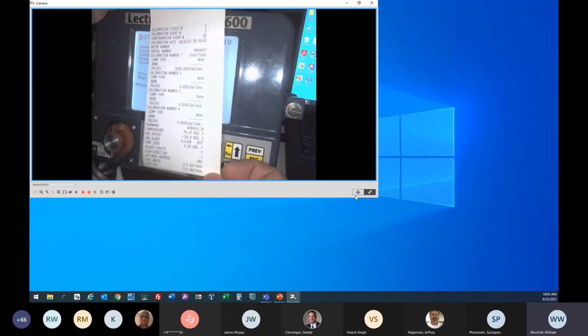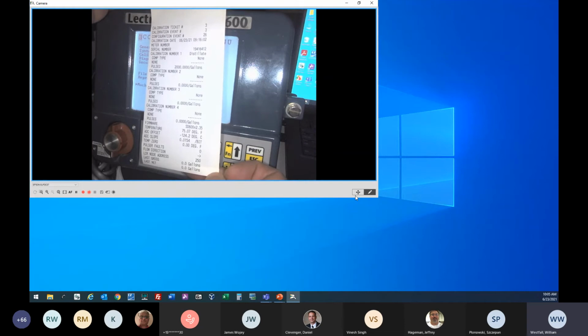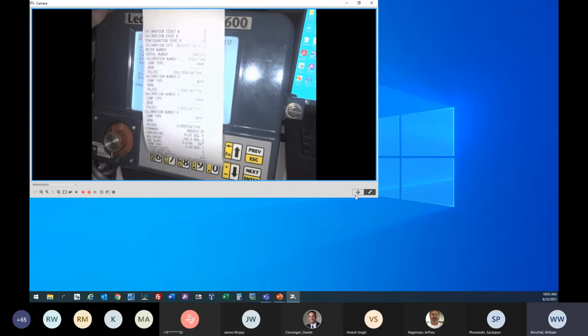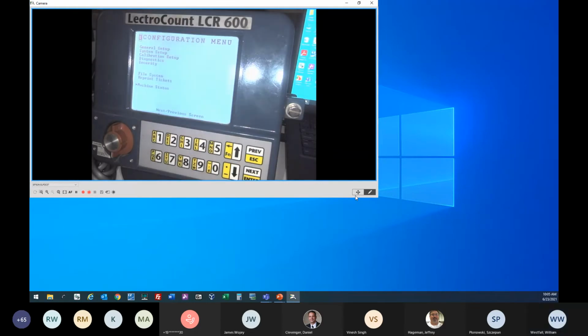Once you do that, you're going to get a calibration ticket to print out. It'll look just like this. You're going to have the calibration ticket number, event number, configuration number, and all the calibration factors on there. That's the first thing to do. Once we get into calibration, you're going to see the configuration menu start up. We want to arrow up, and all I'm doing is hitting this up arrow button into the calibration setup menu. Go ahead and hit the enter key, and we'll enter into the calibration setup.